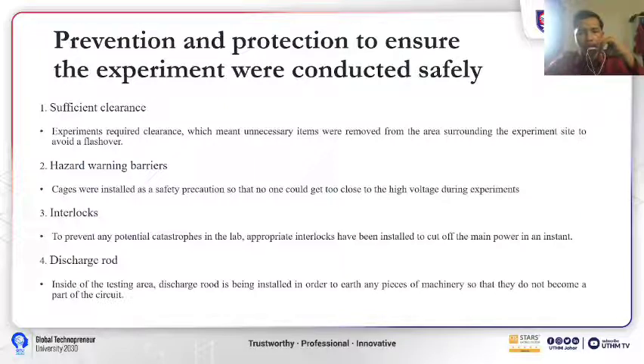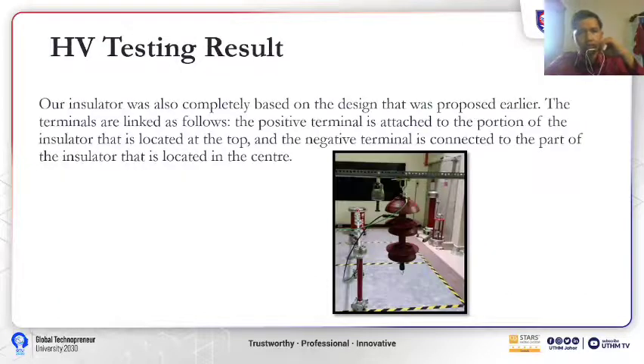Appropriate interlocks have been installed to cut off the main power in an instant. And last, discharge rod. Inside the testing area, a discharge rod is installed in order to earth any pieces of machinery so that they do not become part of the circuit. And for the high voltage testing result, our insulator was completely based on the design that was proposed earlier.